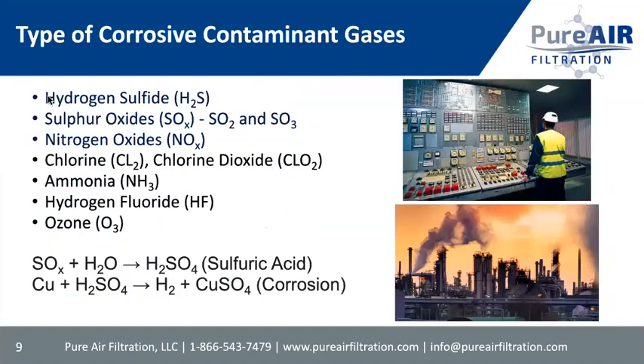These are the problem gases that we see the most. I would say in Asia, it's these top three. That's largely from your own factory could be creating these problems and generating gases that come back into the control room or into the server rooms. Your neighbors could be creating it. In Asia, there's a lot of diesel cars, trains, others that are polluting the air around your building. A lot of two-stroke engines from motorcycles and tuk-tuks and the like, and all of that is creating these problem gases to a lesser degree, but still important.